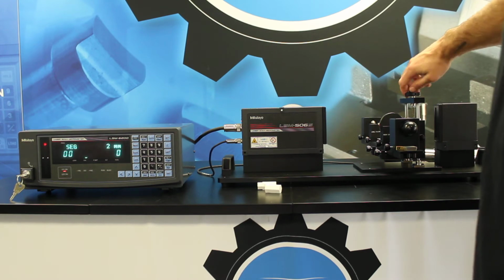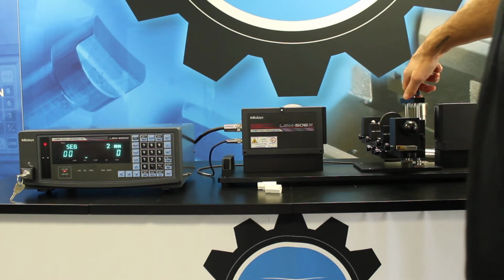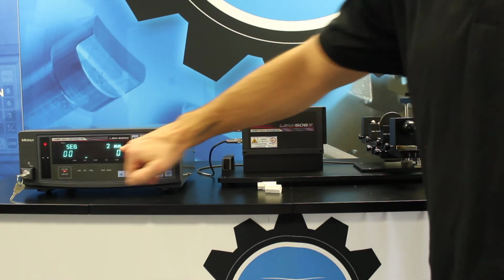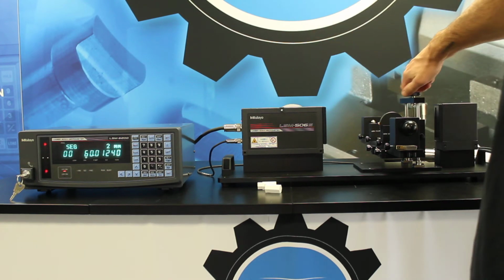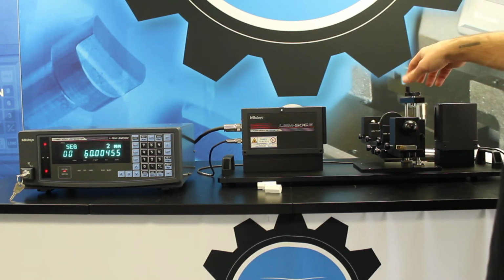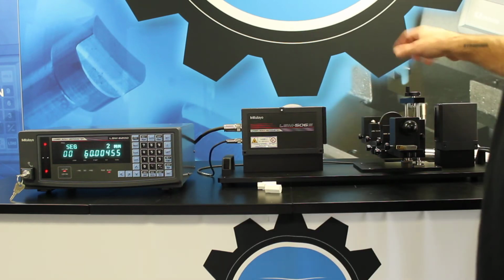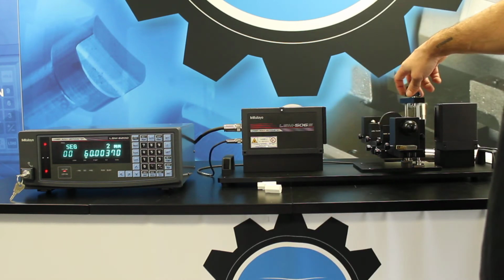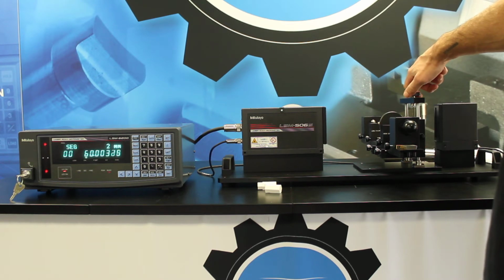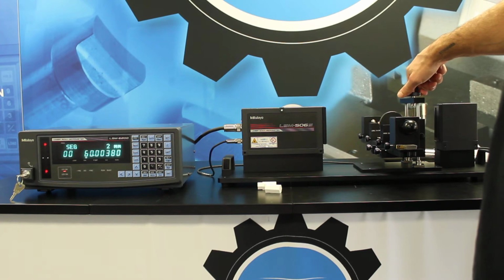At this point, I'm ready to raise my work stage. You'll notice that there's currently no reading on the display, and that's because I am not at the proper height. Once I reach the proper height, I will see a reading pop up on the display, and I know I'm getting closer to where I need to be. So what I'm going to do is continue to raise this work stage until I reach the max reading.